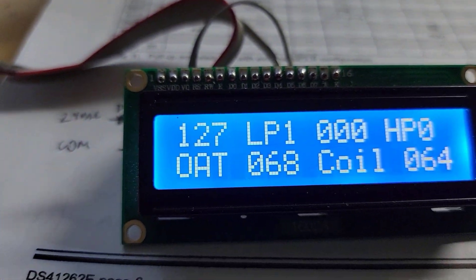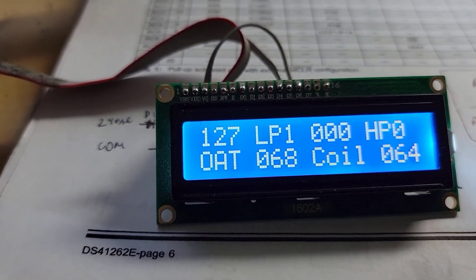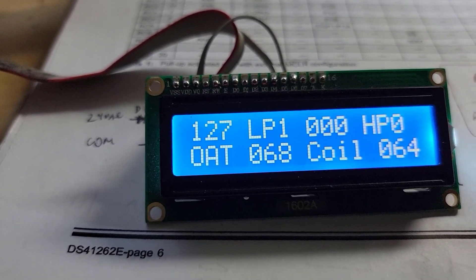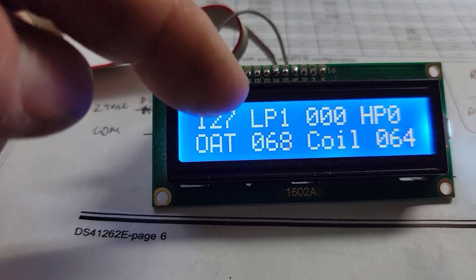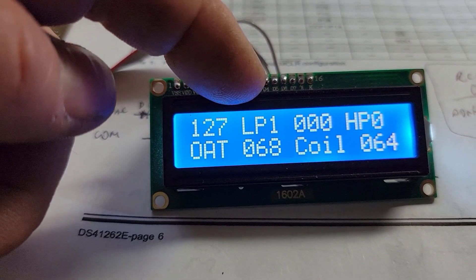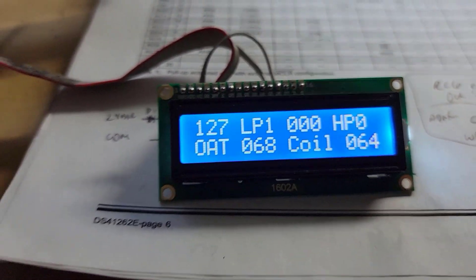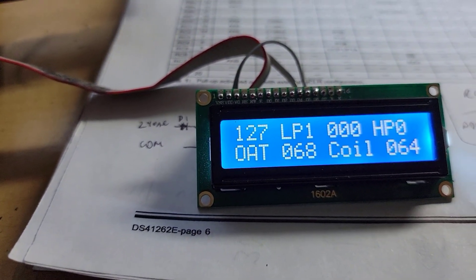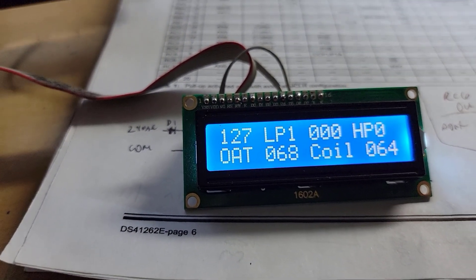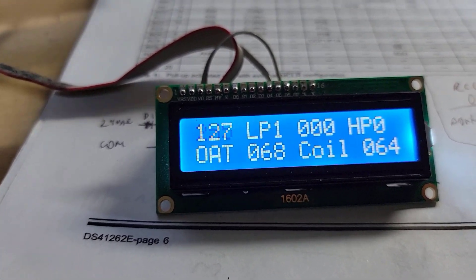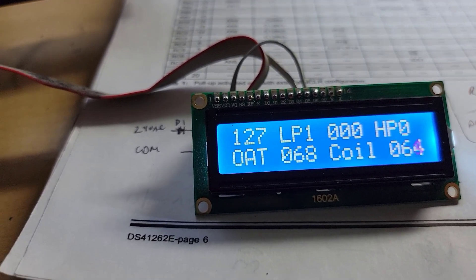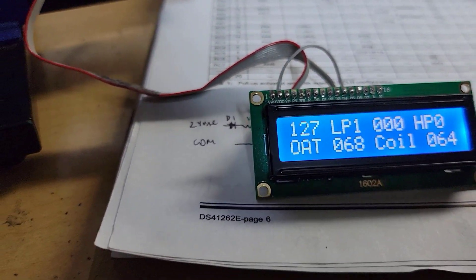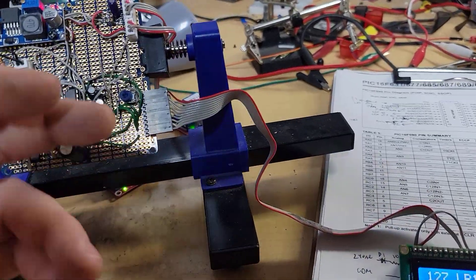So I'm going to go to low pressure in there. See the counts like a voltage divider. So when that continuity is closed, it brings it up across the threshold that satisfies that the low pressure switch is closed. But it will not have enough analog counts to register as a button press. So I push the button, it goes to 255. So in my subroutine, I'll look for that higher threshold to be a button press.